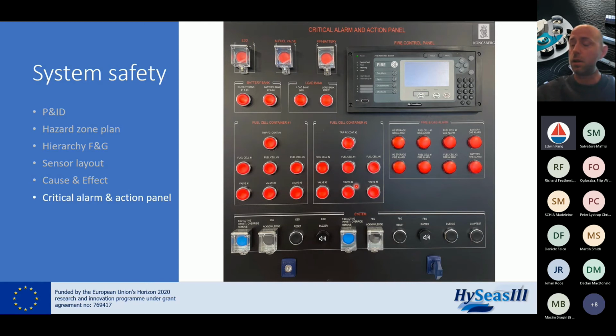Of course, we did 100% safety tests before running the plant in an operational state. We did commissioning and conditioning of the fuel cells together with Ballard, but prior to longer runs, we had everything tested, each sensor with hydrogen, flame detectors with a flame simulator. So we were quite confident it would work, and immediately, a couple of months after, it actually did leak. So it was nice to see it going correct.